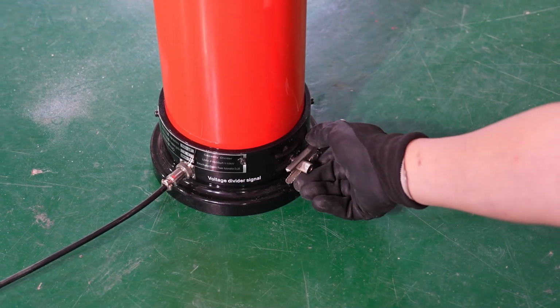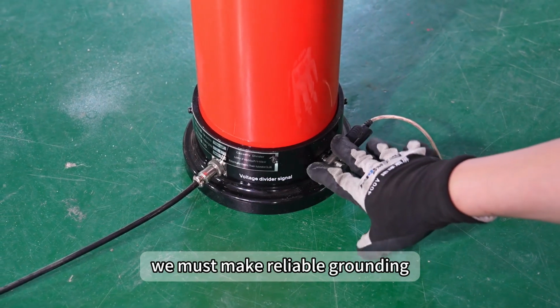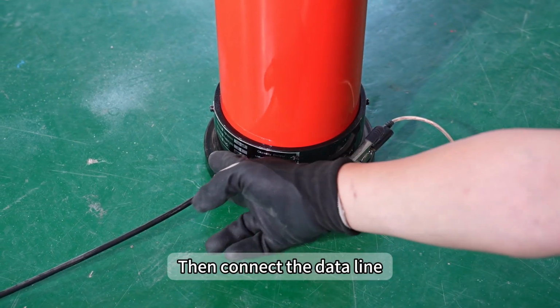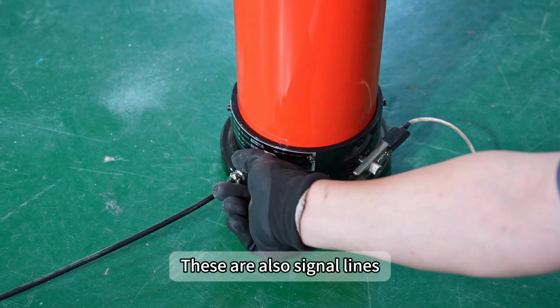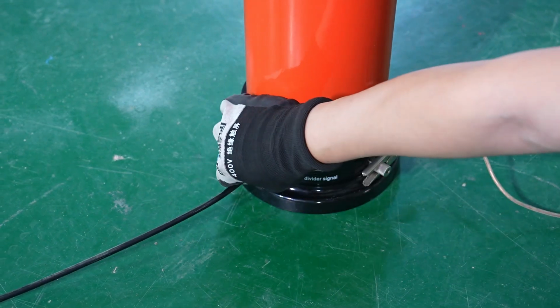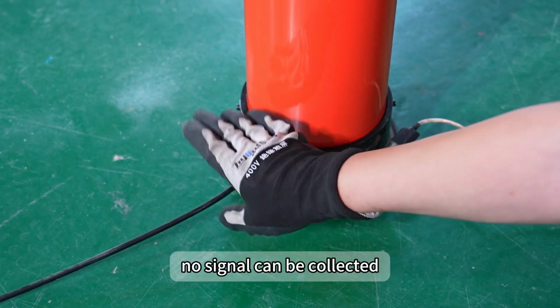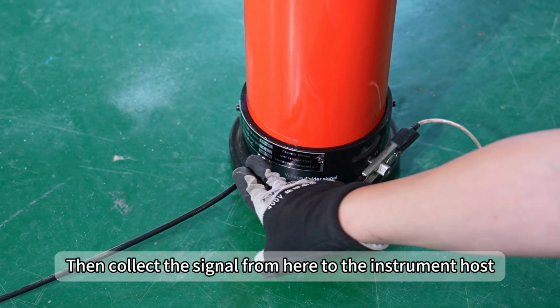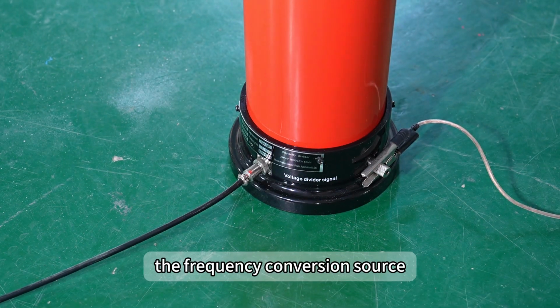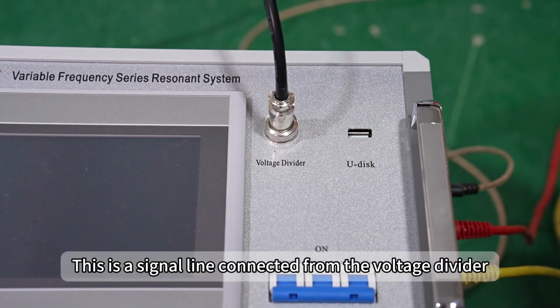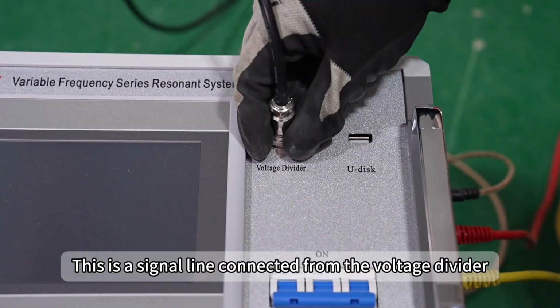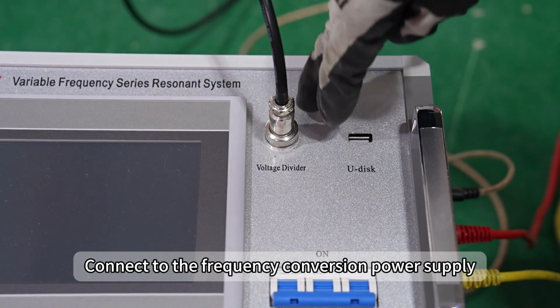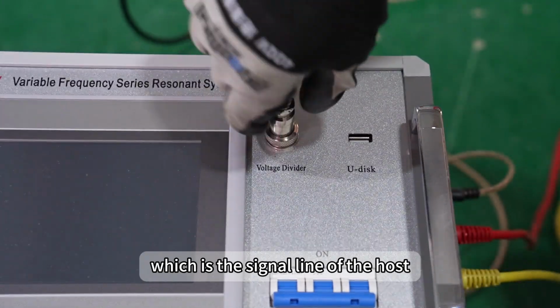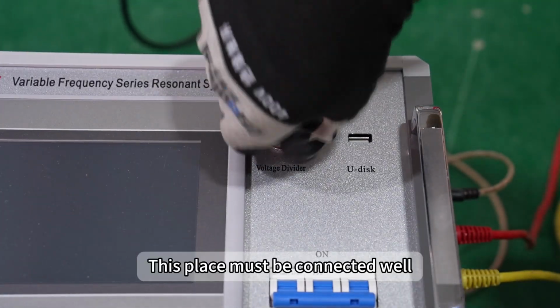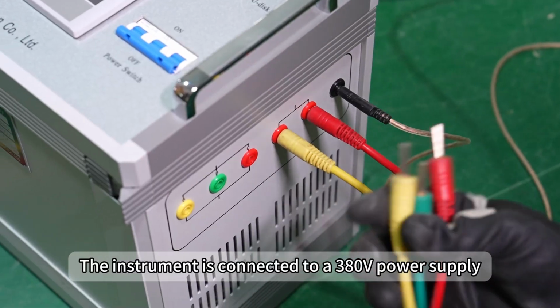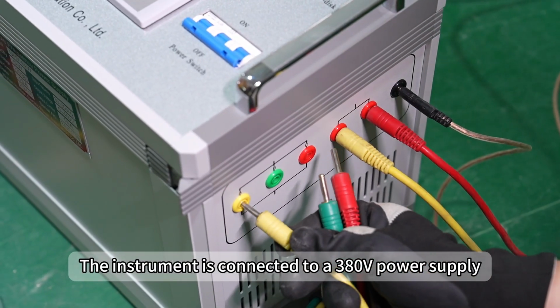Booster wiring. First, we must make reliable grounding. Ground here, then connect the data line. These are also signal lines. Make sure to connect well. Otherwise, no signal can be collected. Then collect the signal from here to the instrument host, that is, the frequency conversion source. This is a signal line, connected from the voltage divider. Connect to the frequency conversion power supply, which is the signal line of the host. This place must be connected well, plug it tight. The instrument is connected to a 380V power supply.